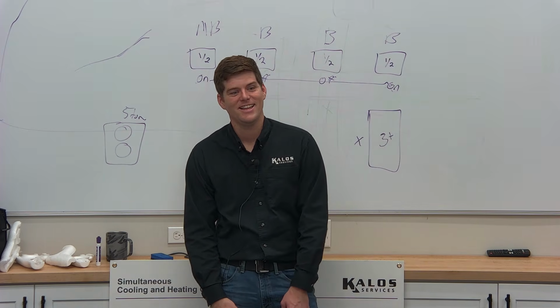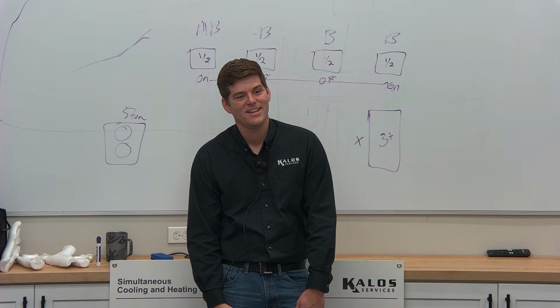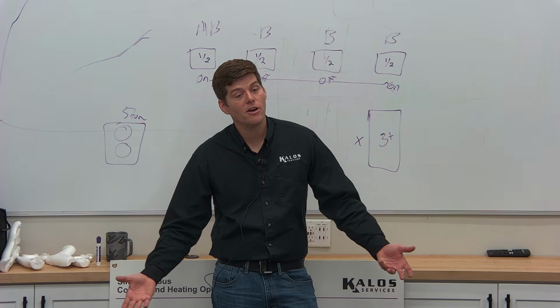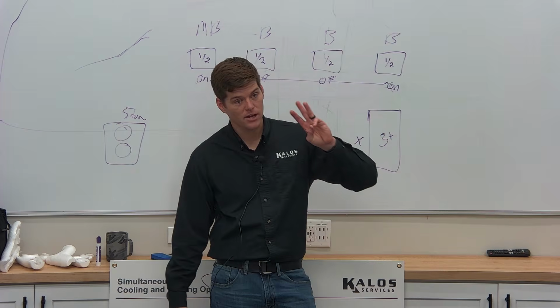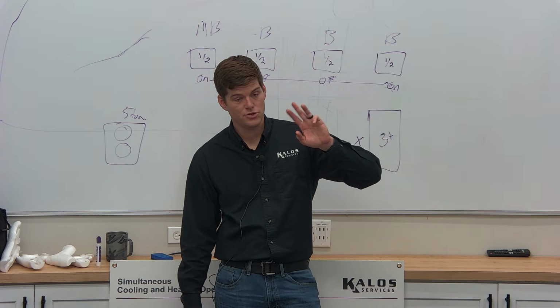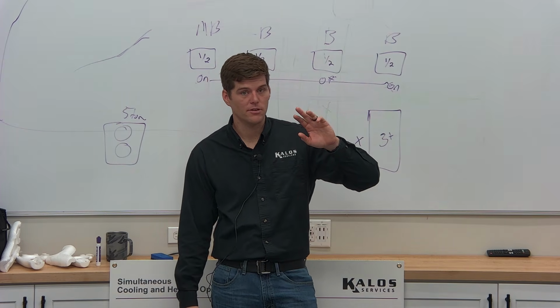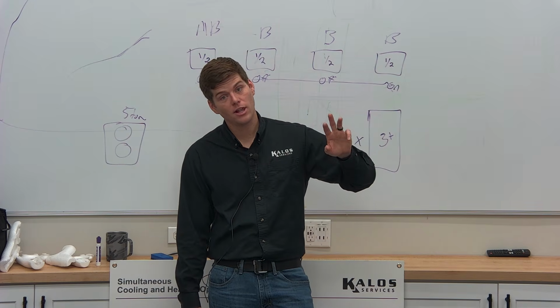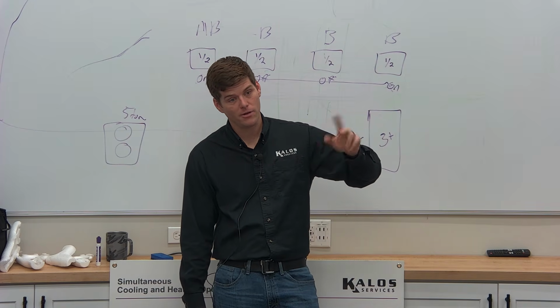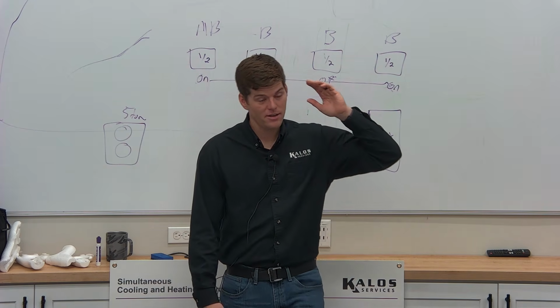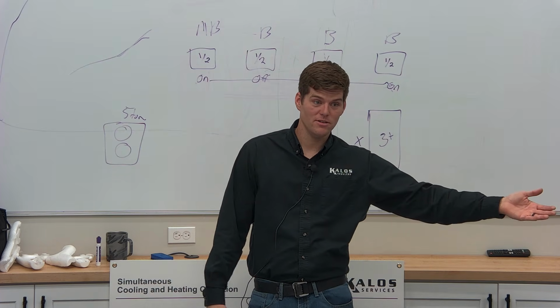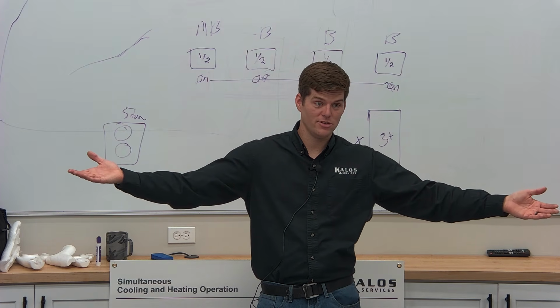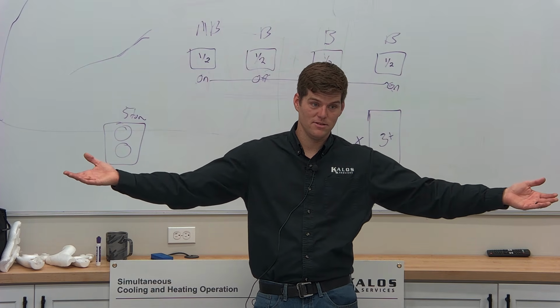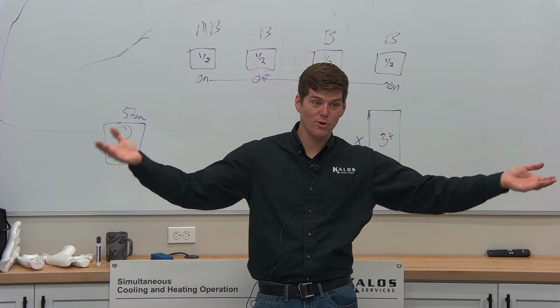Copper needs to be thick enough or strong enough to hold though. When we get into VRF, we have that third line, right? Which usually isn't flared on, it's usually brazed on, but you have that third line that can go from hot to cold in a matter of 5 minutes. We can go from a 45-degree suction line to a 165-degree discharge line in 5 minutes. What happens when things go from cold to hot?